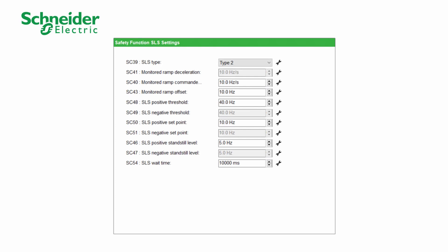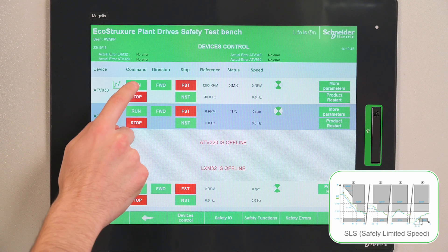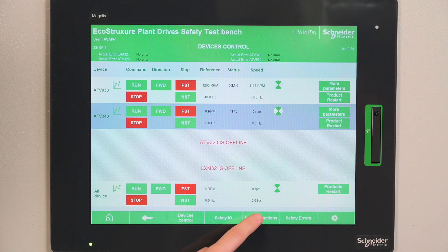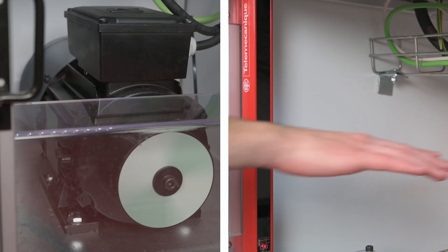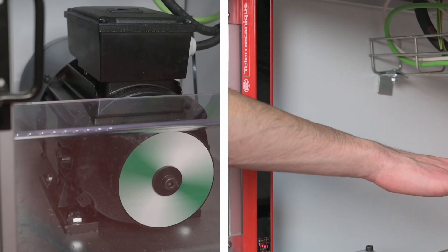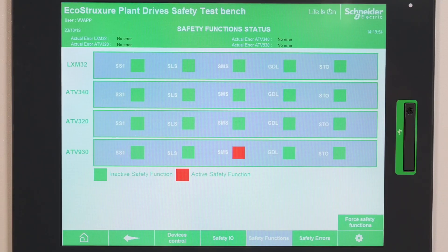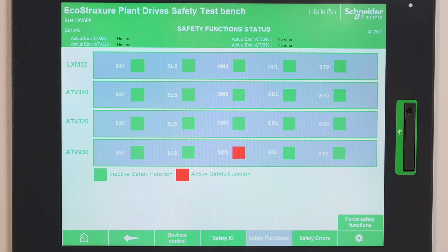We configured SLS using SoMove. We give a run order to the motor. By crossing the safety light curtain, the SLS safety function is activated. We can see the function activation on the HMI and the motor is running at limited speed. By pulling the hand out of the safety light curtain, the SLS function is deactivated and the motor returns to its initial speed. We can see the deactivation of the function on the HMI.